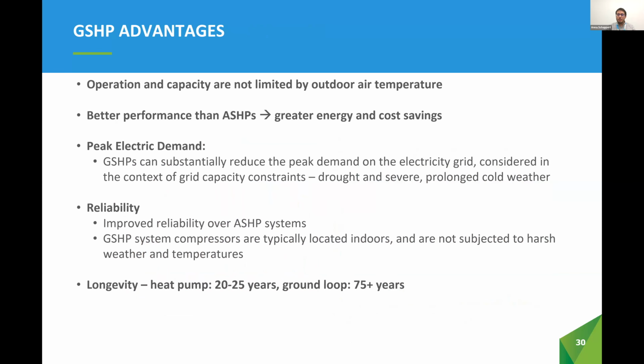So ground source heat pumps have numerous advantages compared with traditional systems and air source heat pumps. Their operation is not limited by low or high outdoor air temperatures, and they can operate continuously and effectively in conditions outside the capability of air source heat pumps. They offer superior efficiency for best-in-class energy and associated cost savings. And they also provide peak electrical demand reduction compared to electric resistance or air source heat pumps, which is an important consideration for our province, especially as we approach the context of capacity constraints due to load growth, as well as prolonged drought or severe cold weather.